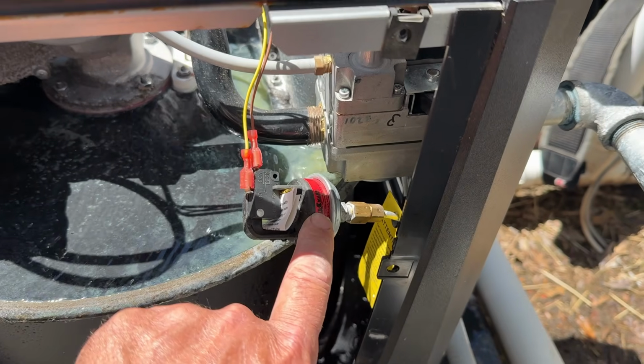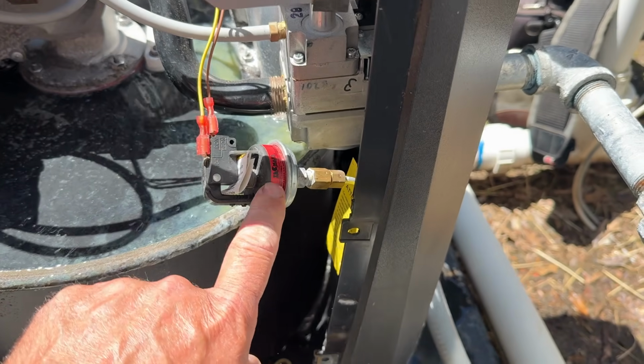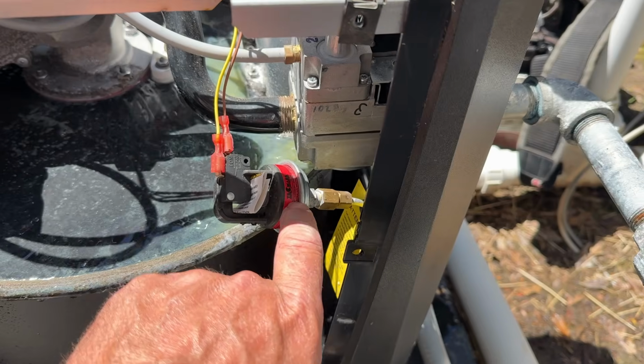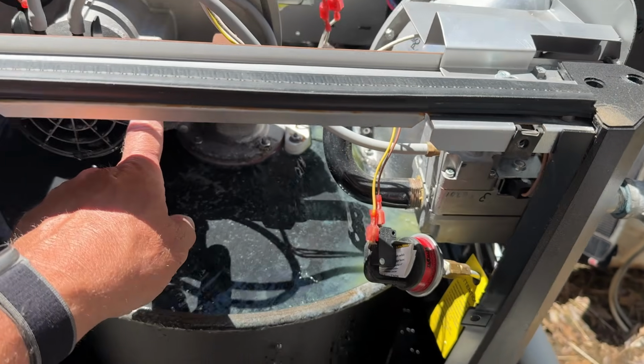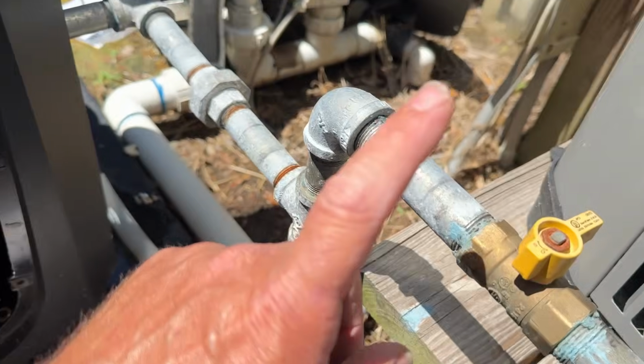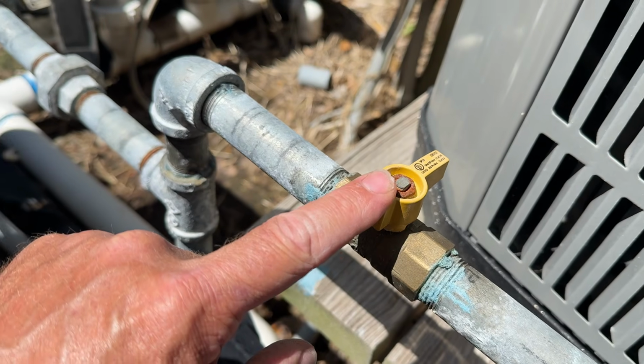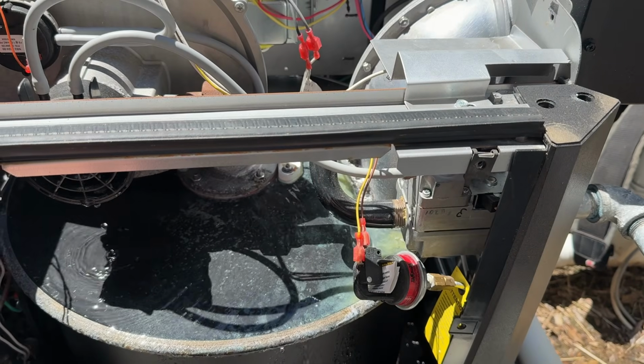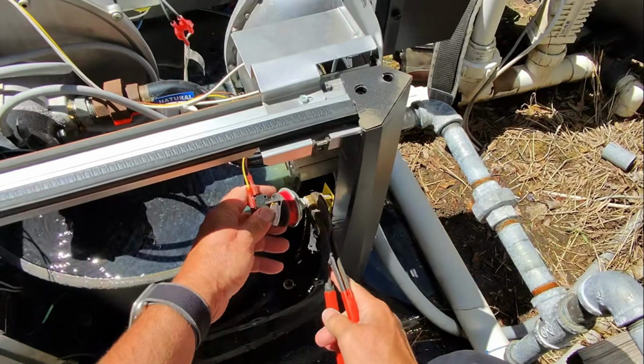Let me take off my gas pressure switch. You got water coming out of the gas piping because it's backfeeding into the gas valve. Thank God the pool company were smart enough to close the gas valve off when they saw something wrong with this. Take a look at this, guys.